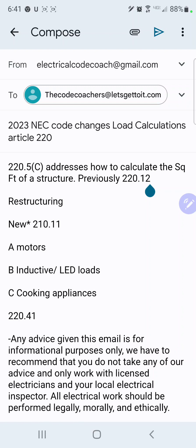It says the floor area for each place shall be the outside dimensions of the building or dwelling unit or other area involved. For dwelling units, the calculated floor area shall not include — and this is where the huge change comes. It used to be in the 2017 code that the square footage did not count for open porches, garages, or unused or unfinished spaces that are not adaptable for future use.